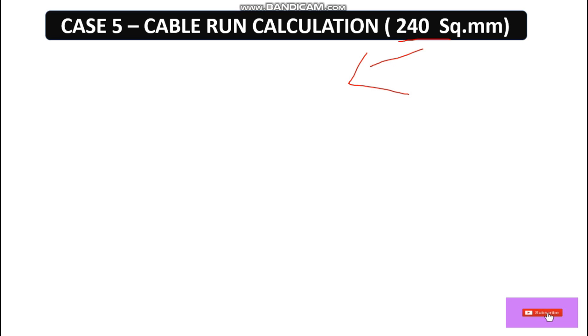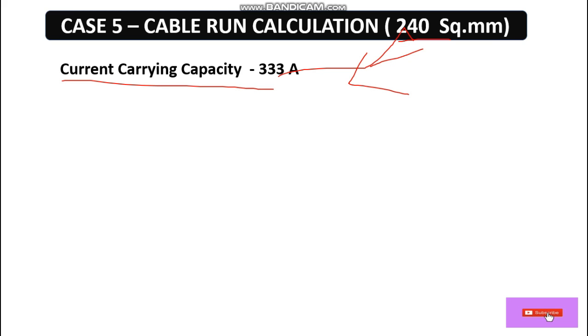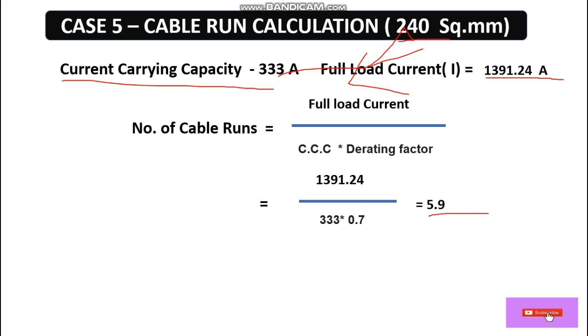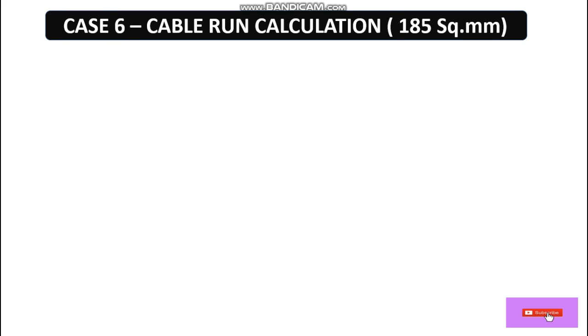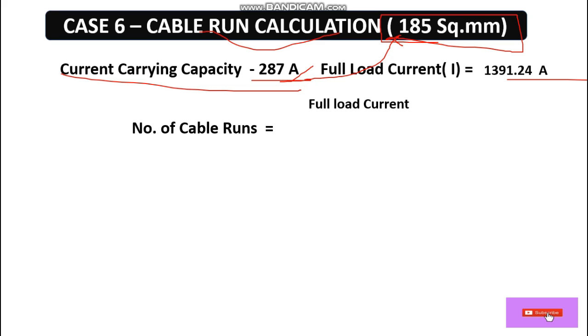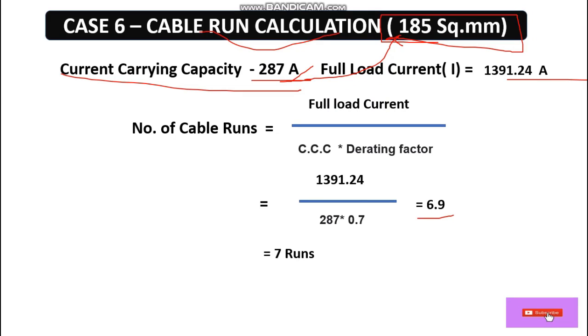Case 5: For 240 square mm cable, the current carrying capacity is 333 ampere. Full load current is 1391.24 ampere. Cable run = 5.9, meaning 6 runs are required. Case 6: For 185 square mm cable, the current carrying capacity is 287 ampere. After calculation, 6.9 runs are required, meaning 7 runs are needed.